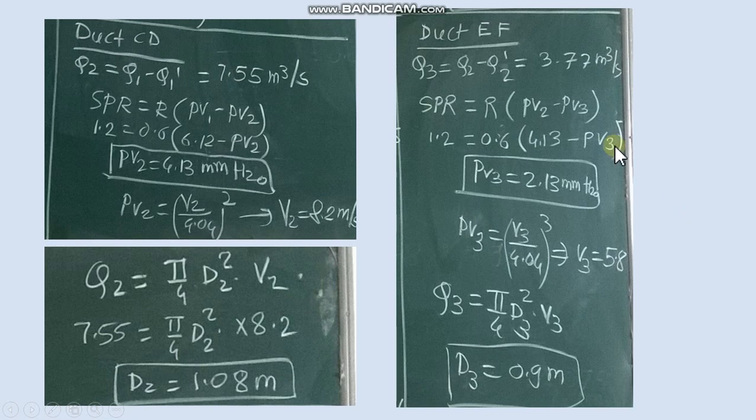So Q2 dash is 3.77. So in EF duct we get discharge. Then from SPR formula we get dynamic pressure in 3rd duct. From this we get velocity in 3rd duct. Then 3rd duct velocity and 3rd duct discharge we get diameter of 3rd duct.